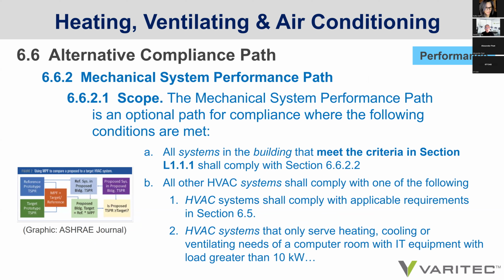But there is now a new alternative performance compliance path for section 6 in mechanical systems, and it's called the Mechanical System Performance Path. It is an optional path for compliance where the following conditions are met. All systems in the building that meet the criteria in section L1.1.1. L is one of the normative appendices within the standard itself, so language is provided on how to actually use the mechanical system performance path. All other HVAC systems shall comply with one of the following, as outlined below, in regards to the requirements of section 6.5, as well as systems that serve heating, cooling, or ventilating needs of a computer room as outlined previously.